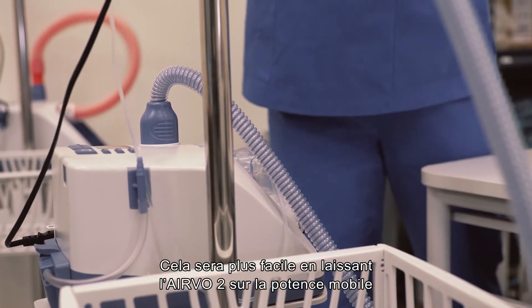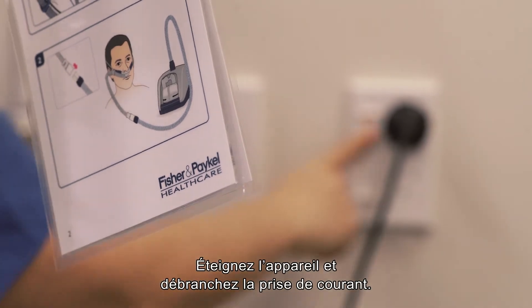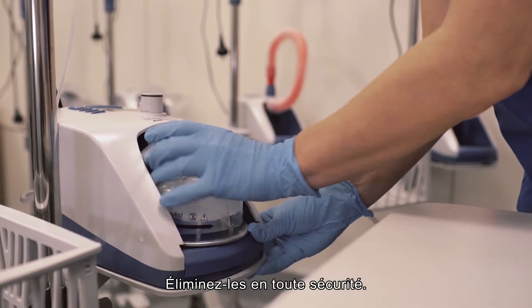It's easiest if you leave the AIRVO 2 on the mobile pole stand. Switch off the unit and unplug from the mains utility power socket. Remove the breathing tube, water chamber and water bag and safely dispose of them.